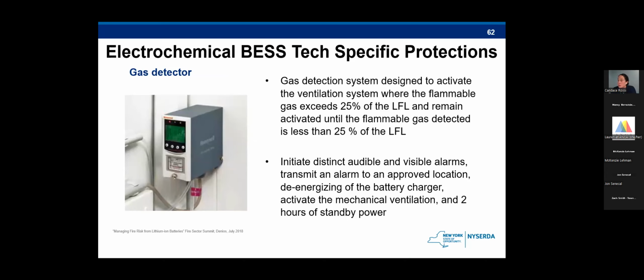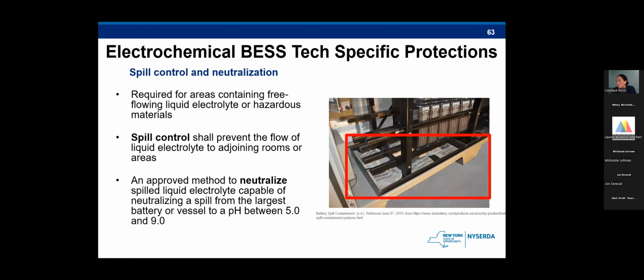So some energy storage chemistries have a liquid corrosive electrolyte. And these corrosives can burn skin and damage first responders' PPE. So the responders should follow their department's standard operating procedures when responding to any corrosive spills regarding energy storage. So basically this is required. Lead acid is an example of batteries with a liquid electrolyte. So they have to make sure that they have this specific spill control and neutralization implemented on site for those projects.